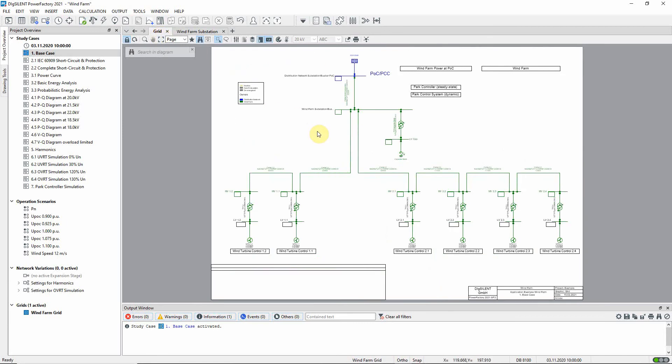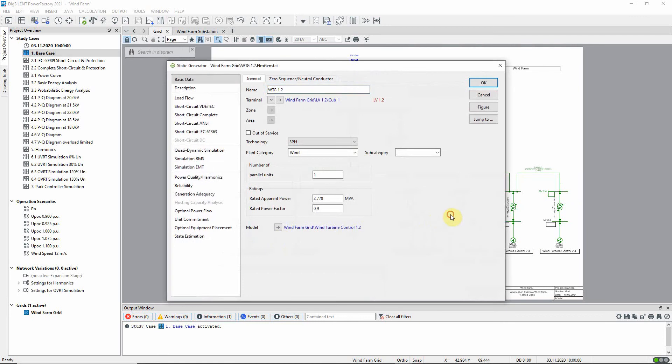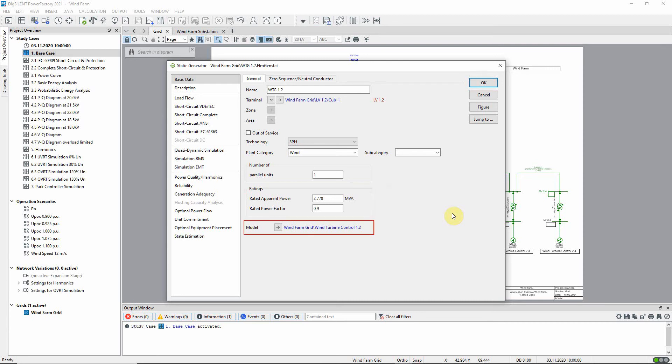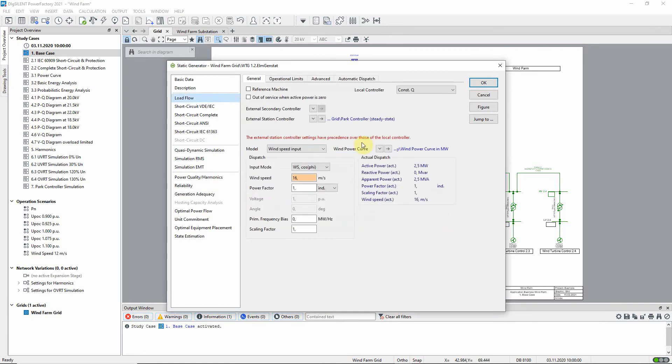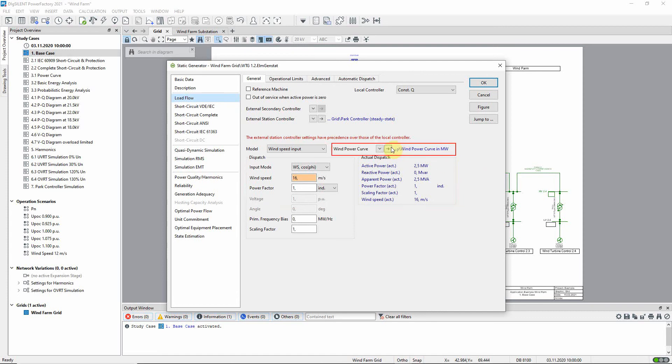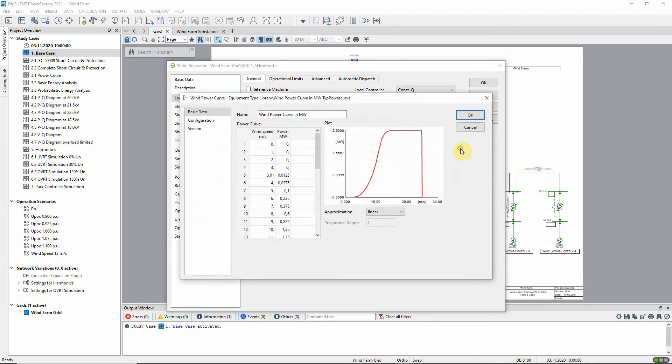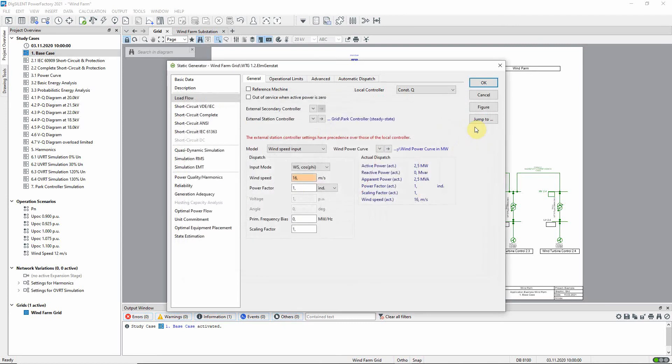The wind turbines are all identical. They have a nominal apparent power of 2.778 MVA and a nominal power factor of 0.9. A dynamic model has already been assigned to each of the wind turbines and this can be accessed via this arrow. On the load flow page you can see that the active power output is to be defined according to wind speed using this wind power curve.